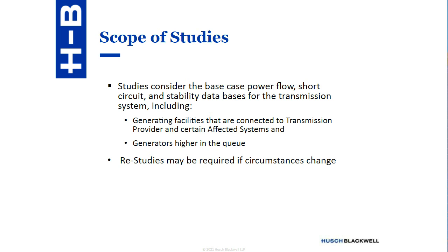Also, delays in any of these studies could occur at any time. The transmission provider is required to notify the interconnection customer of any delay with an estimated completion date. And if requested, the transmission provider will supply supporting documentation, work papers, and relevant pre-power flow, short circuit, and stability databases for the system impact and facilities studies, subject to confidentiality agreements.